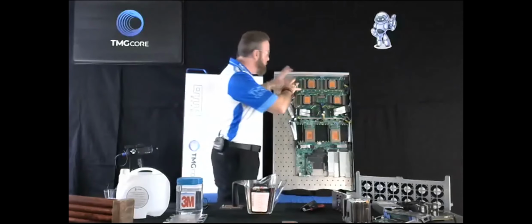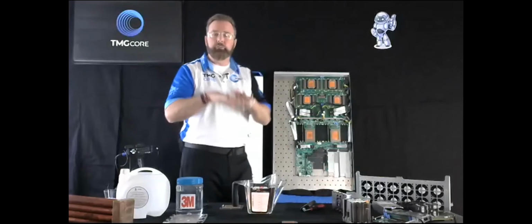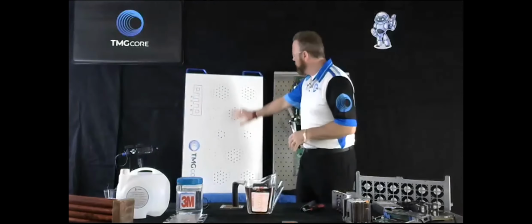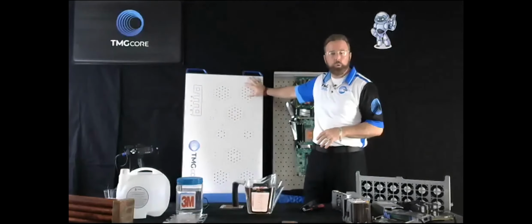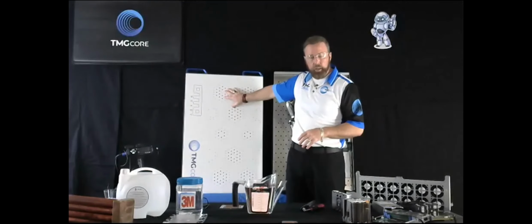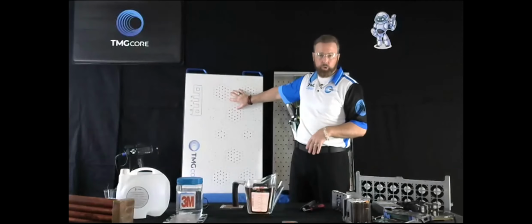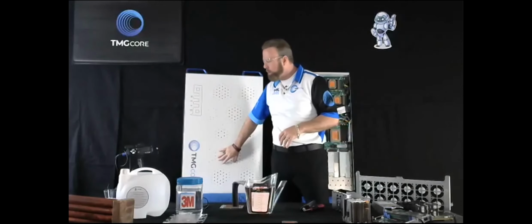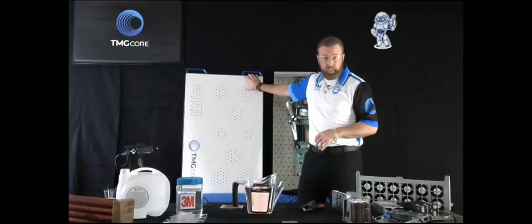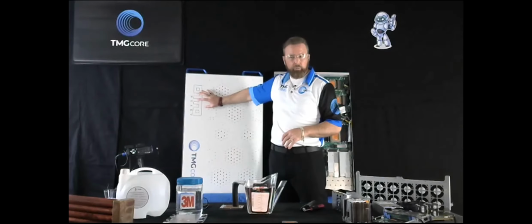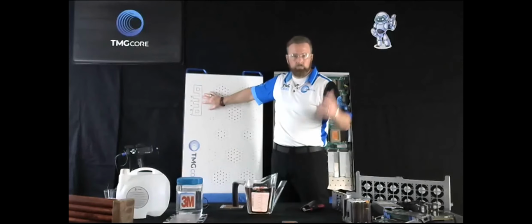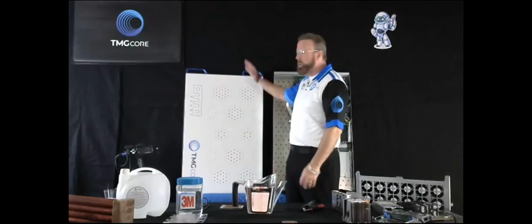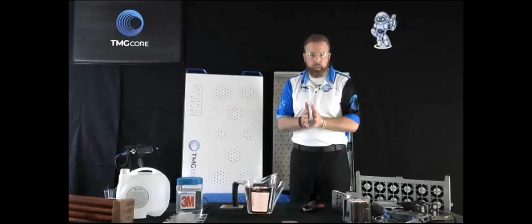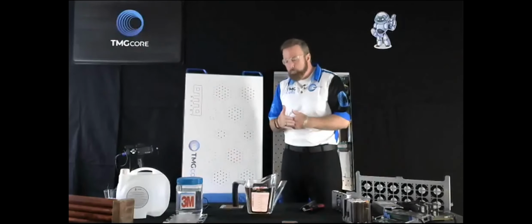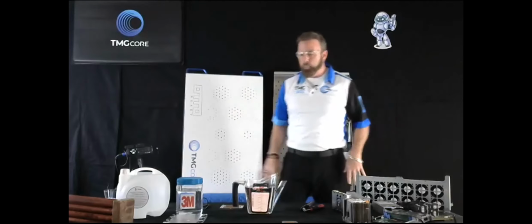For that case, we want to make things really, really dense to make the value proposition right. This is what we call the G1611, a 6,000 watt 1U server that we can overclock to 7,300 watts. Look at our GPU chip temperatures — I think we have 16 NVIDIA Tesla V100 GPUs in this 1U server with 2 Xeon Intel CPUs, and we can overclock this at 7,300 watts with chip temperatures around 82 degrees Celsius, which is below what it's rated to run in air. So we're able to get extremely high densities, and all of a sudden you've got a lot of compute in a very small space, which makes the value proposition. The more the industry works towards that, the more sense this all makes and will continue to make.